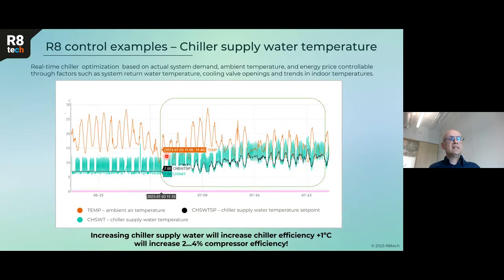Okay, next example. For example, the chiller. Most of the chillers are using a static supply water temperature setting. In most cases in Nordic countries, it's +7. What we are doing is checking the actual room conditions and actual needs of the rooms, and if the chiller is connected with the ventilation system, we are also checking the cooling coil valve status. And based on that, we are automatically calculating the necessary supply water temperature set point.